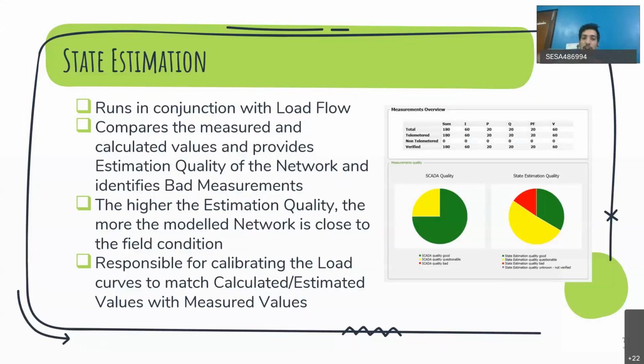Say for example, you wrongly drew the feeder. Because of that, some unnecessary mesh has formed. Because of that, measured data is correct, but calculated data is wrong. So that way, state estimation will compare both so that you improve the measurement side in the field and you improve the calculated side in the control center also.